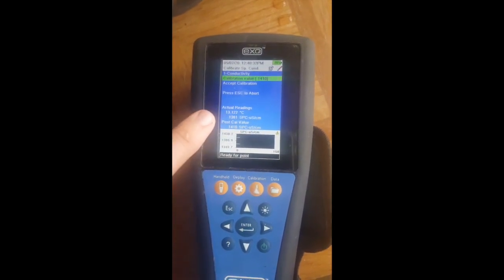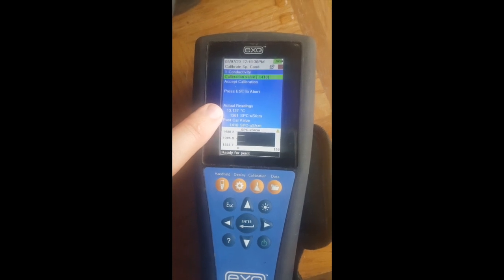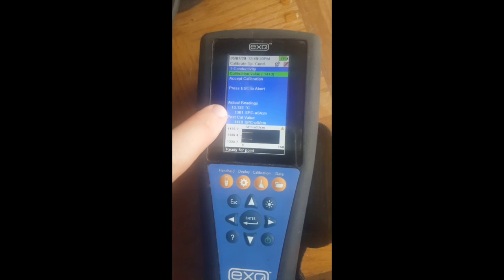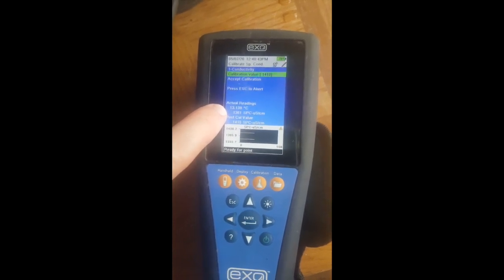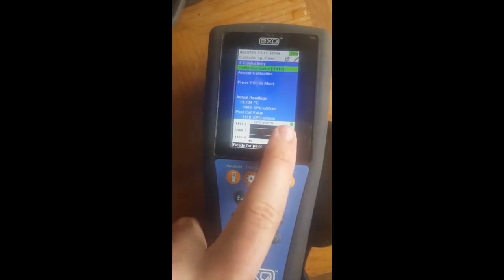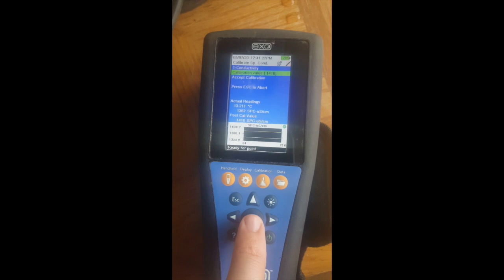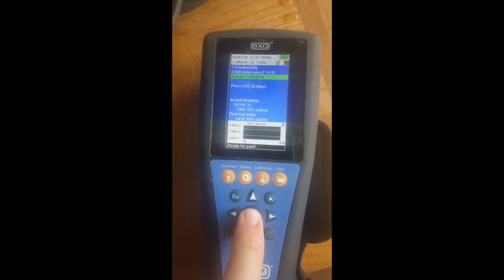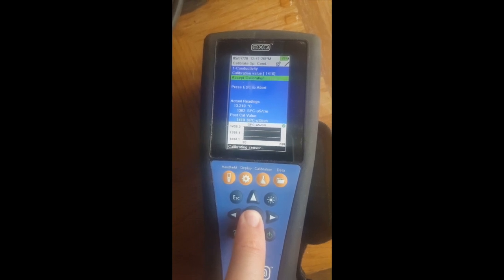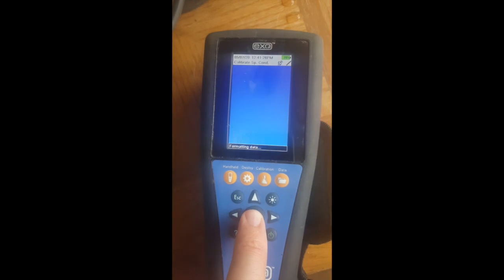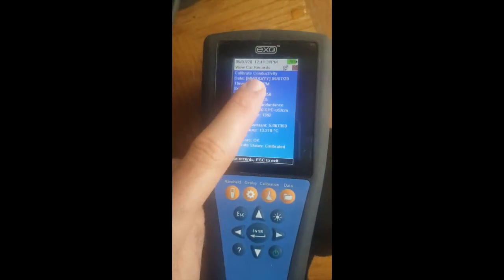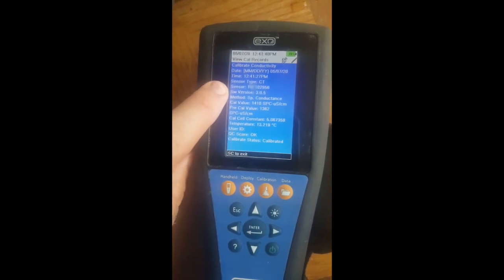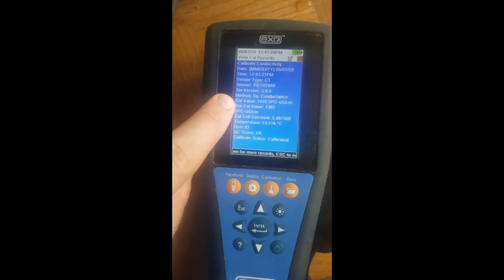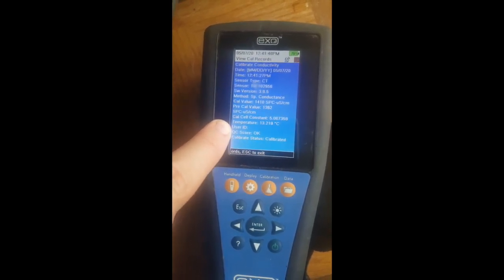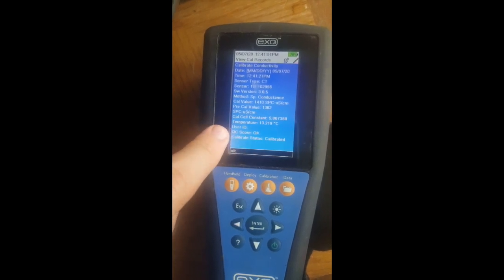We're going to enter in our calibration value. We're going to watch our actual readings with what we want to calibrate it to and see if this number, the actual readings, changes. We got the green check mark. We'll push OK. So we have the time, what our calibration value was to, or pre-cal value, and we got a QC score of OK, so it gives me confidence that we got a good calibration value.